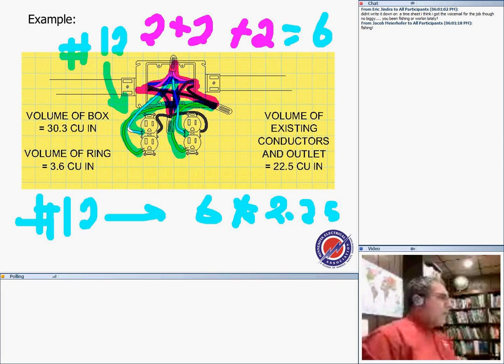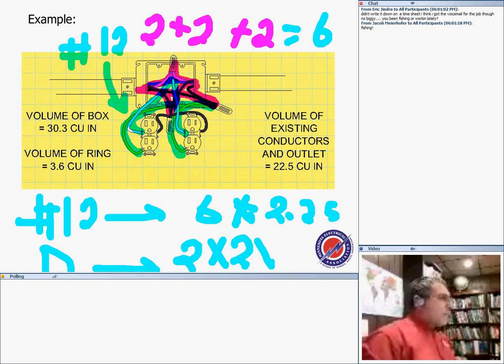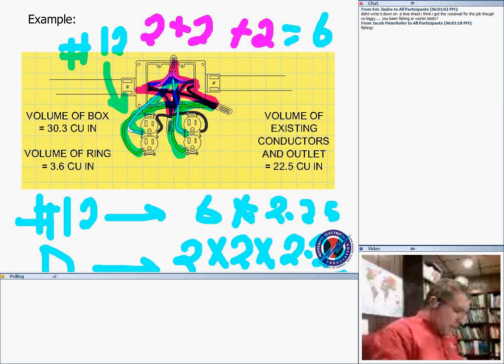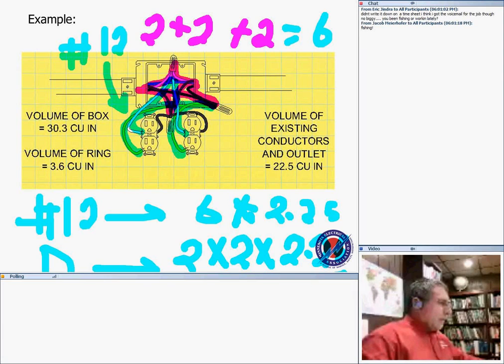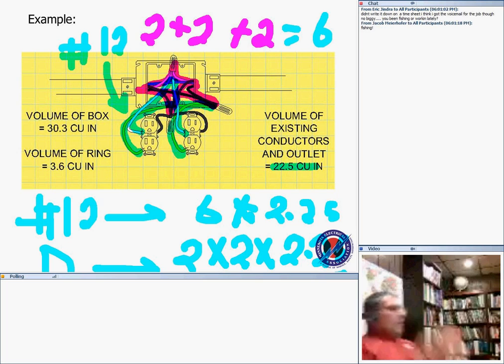I have 6 number 12 conductors, and if you go to number 12, the multiplier is 2.25. Okay, how many devices? I have 2 devices, right? 2 receptacles, multiplied by 2 each, because there are 2 allowances for each, based on the largest conductor ending on them, which is 2.25. You guys do your math on this example. It will be 6 times 2.25 plus 2 times 2 times 2.25, equal to 22.5 cubic inches. That's how many cubic inches all these conductors and devices are occupying.